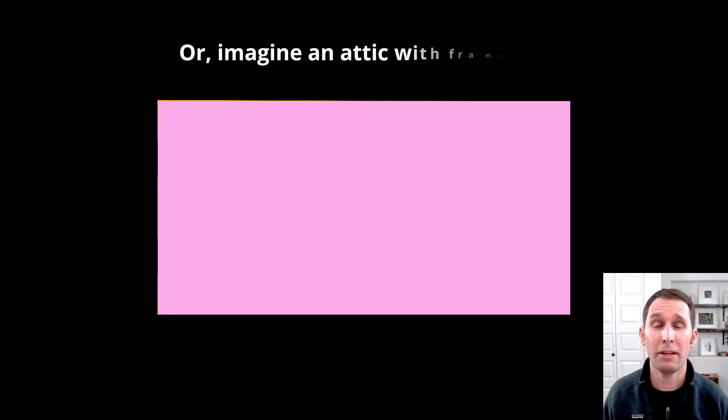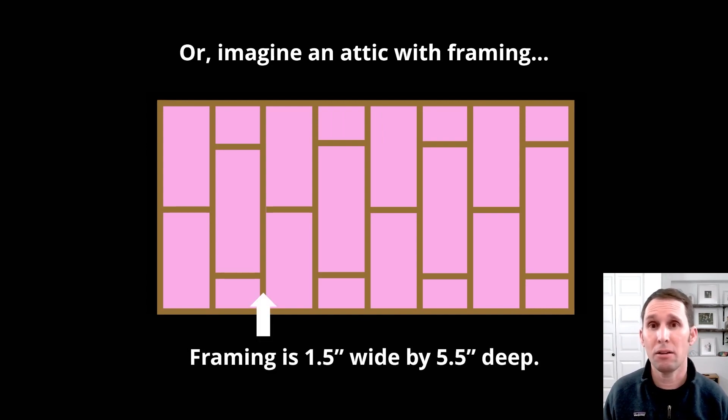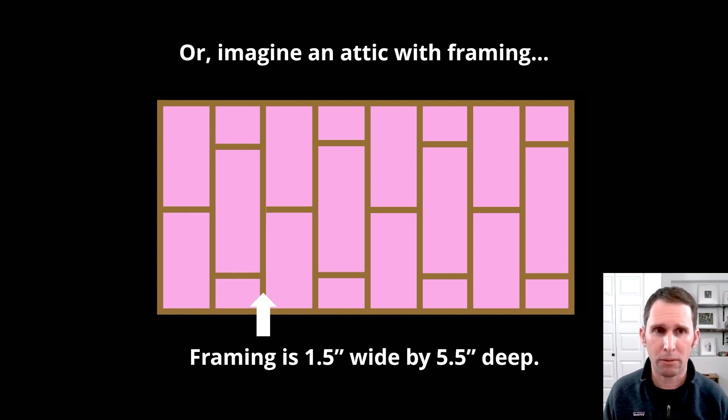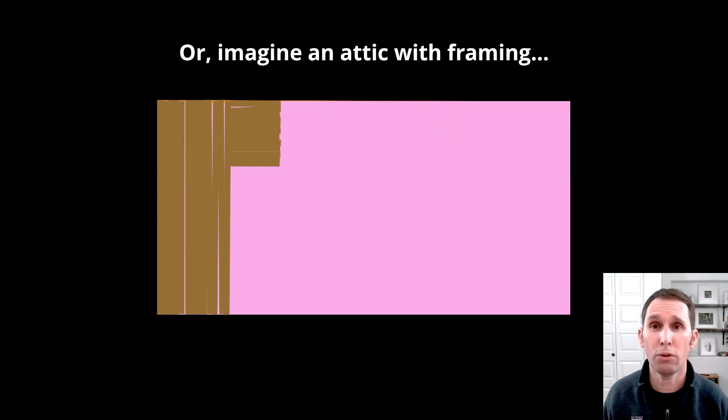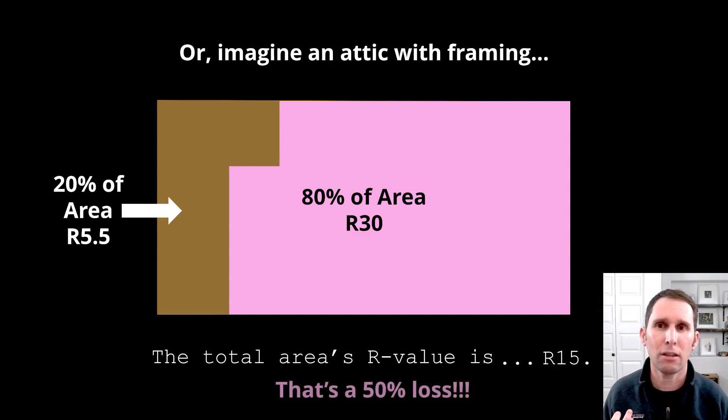So, here's another really common example of when you might lose effectiveness of your attic insulation. Your framing in your attic is 1.5 inches wide by 5.5 inches deep if you had 2x6s on your attic floor. The R value of that would be R1 for wood times 5.5 inches would be about R5.5. And if you add up all those framing components, that may make up 20% of the area. So, now you have 20% of the area of 5.5, 80% of R30 before you even started. That's a 50% loss in insulation. So, it's not just important how much insulation you have. It's very important how well it is installed.